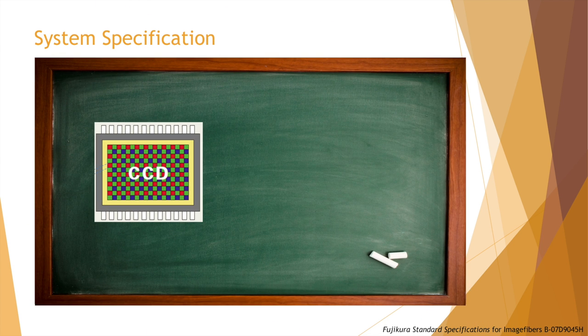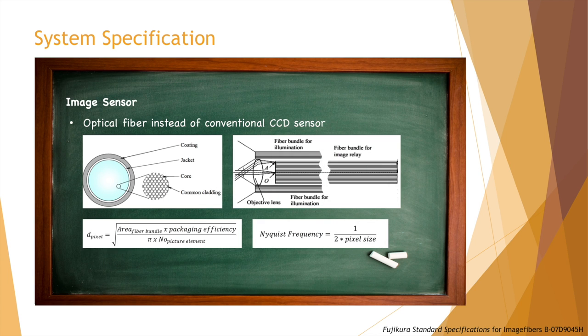Unlike a usual CCD sensor, our sensor is one end of the imaging fiber. It should form a matched image the same size as the fiber bundle. The other distal end is connected to a CCD. The 30,000 picture elements in the fiber bundle give decent resolution and good flexibility. The sensor size is 2 mm in diameter. Considering packaging configuration and efficiency, the diameter of a single fiber — which is also the pixel pitch — is estimated as 11 microns. This pixel size is important for calculating the Nyquist frequency.